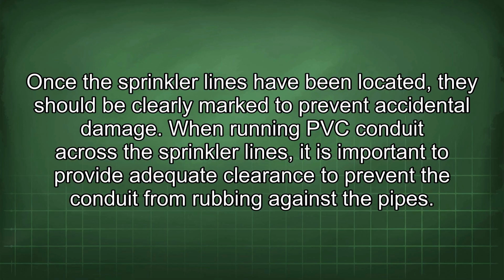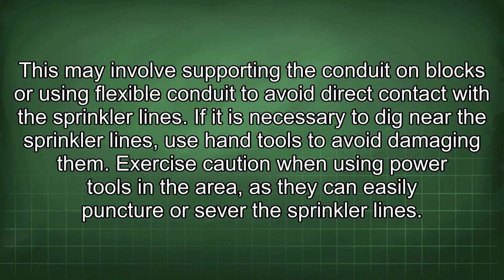When running PVC conduit across the sprinkler lines, it is important to provide adequate clearance to prevent the conduit from rubbing against the pipes. This may involve supporting the conduit on blocks or using flexible conduit to avoid direct contact with the sprinkler lines. If it is necessary to dig near the sprinkler lines, use hand tools to avoid damaging them. Exercise caution when using power tools in the area, as they can easily puncture or sever the sprinkler lines.